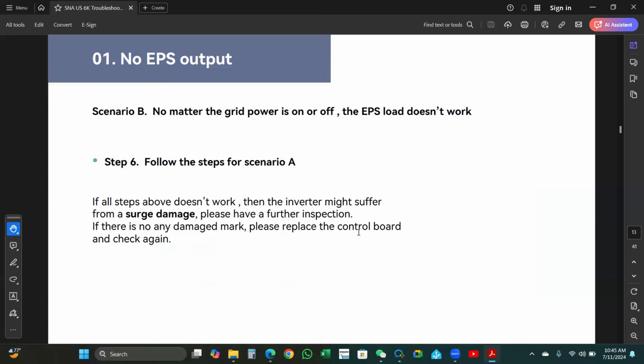Step six, follow the steps of scenario A. If all the steps above don't work, then the inverter might have suffered surge damage. Please have a further inspection. If there is no damage mark, please replace the control board and check again. You can contact me as tech support if you have any problem with this.